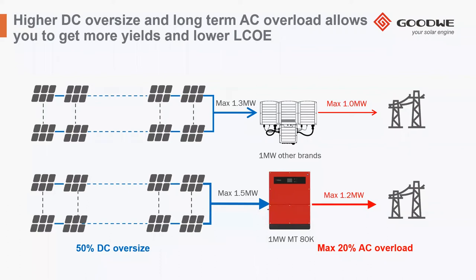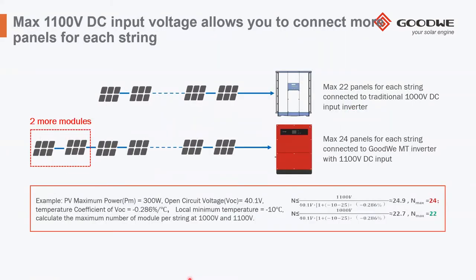Another feature, which I mentioned at the beginning, is that you can choose between the model with 1000 volt DC input or 1100 volt. It's clear the version with 1100 allows you to put 2 more modules per string, as you can see from this calculation here. So again, you can have a longer string, so you can save on the connection cables and all these things. So your configuration will be easier and you can get more power per string to be then fed through the inverter to the grid.